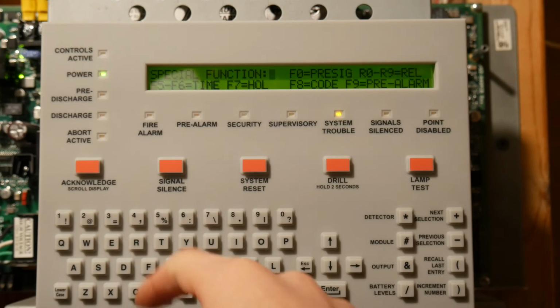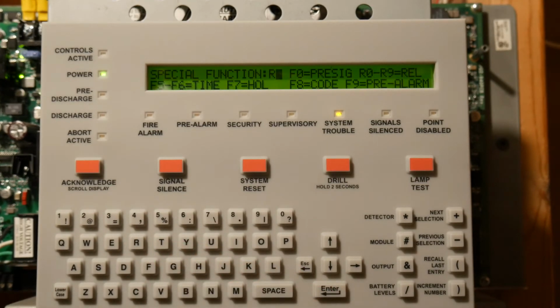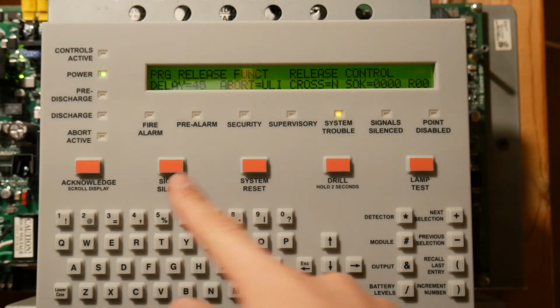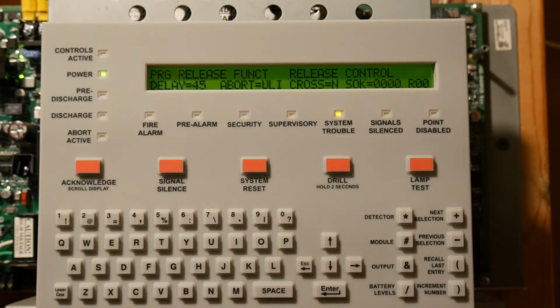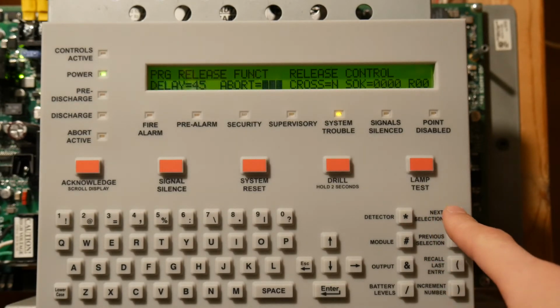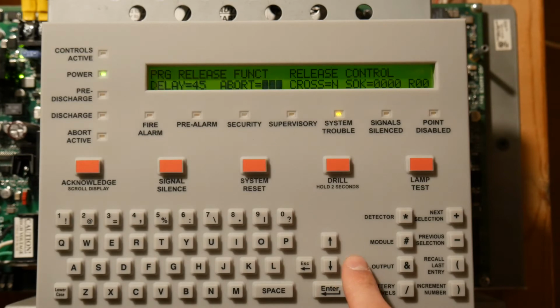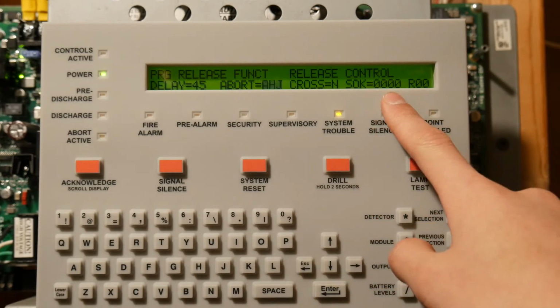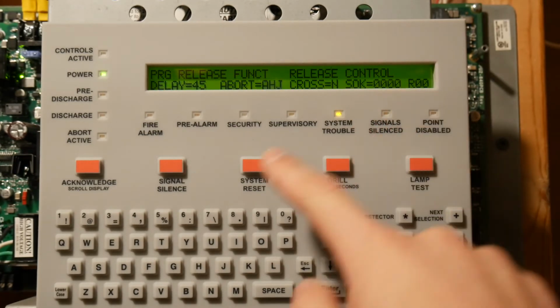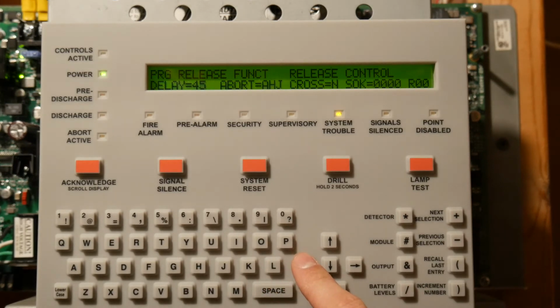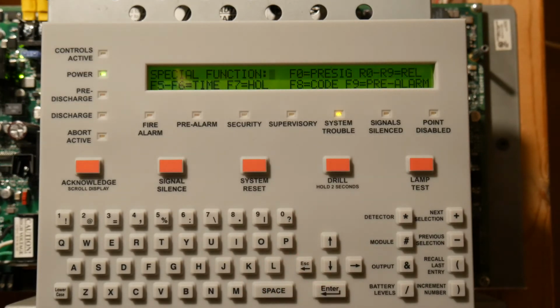Now we're going to go into releasing zone. So we're going to put R0 and it's going to take delay. We want a 45 second delay. Abort, I want our abort set as, let's see, AHJ. So for AHJ, we're going to press 00 and releasing zone 0. So everything looks fine, so we're going to press enter. Enter, save, escape, delete changes.